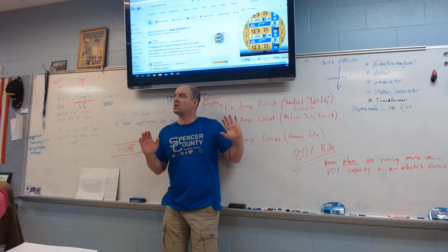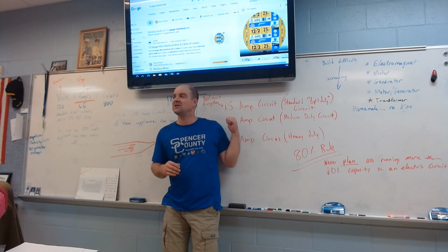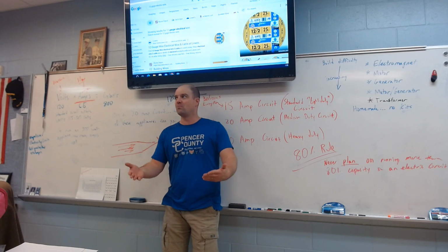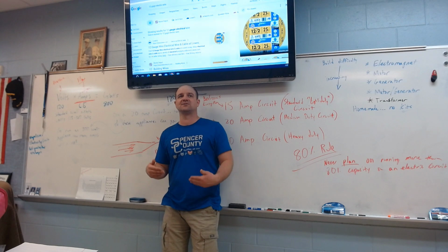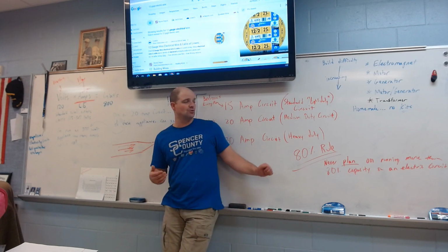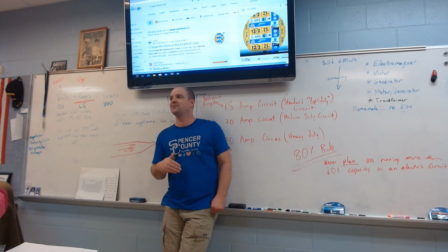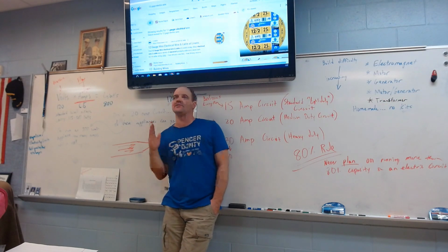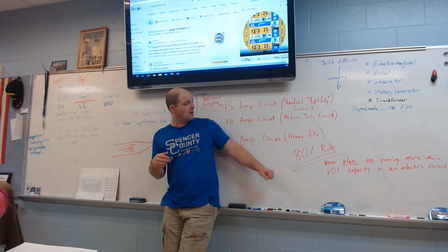So if your circuit is a 15 amp circuit, you probably shouldn't be drawing past like 12 amps constantly, because that wiring is still going to heat up. And what'll happen is if you're too close to 100% capacity, you're going to reduce the lifespan of your wiring. Does that make sense? I mean, imagine if you were going 100% all the time. You're going to burn out, right? As a person. Sometimes you need to back off a little bit. So, 80% rule.